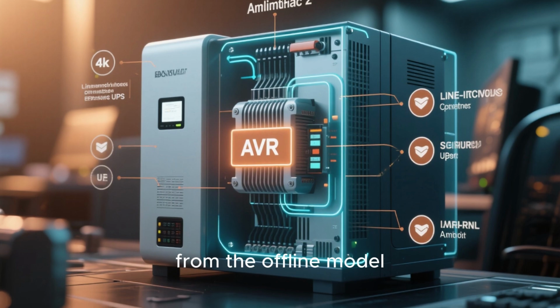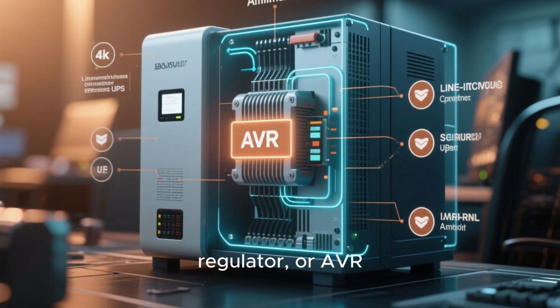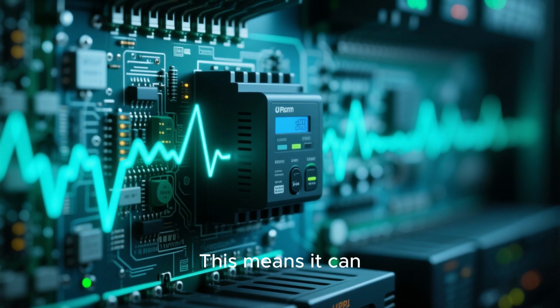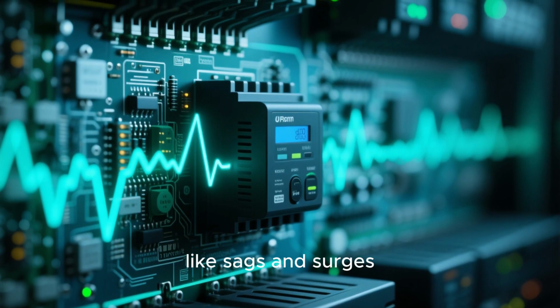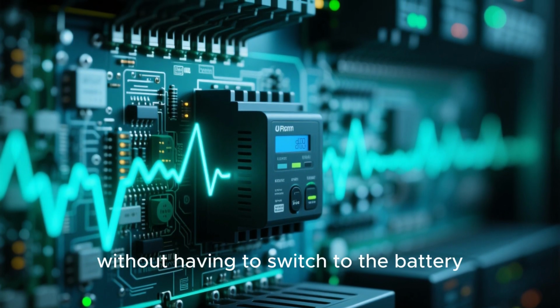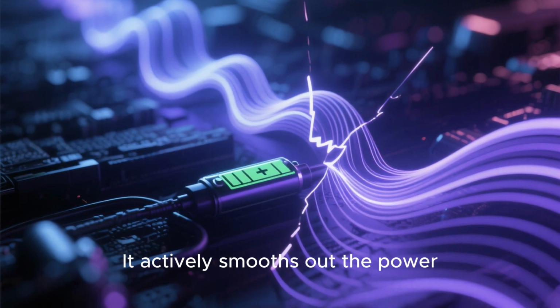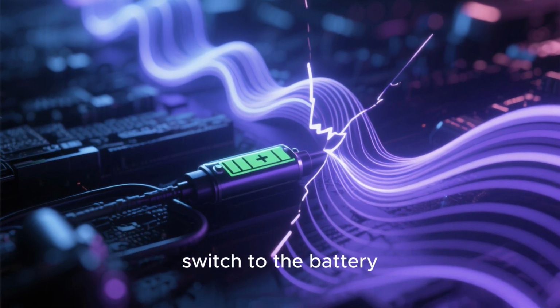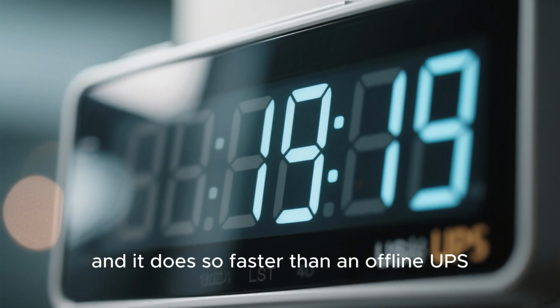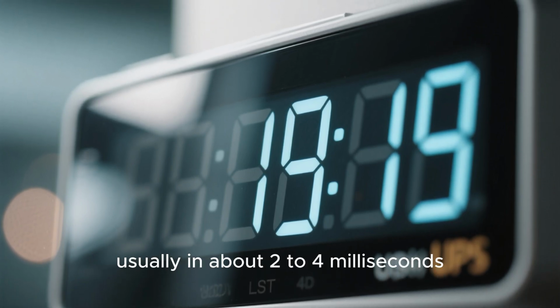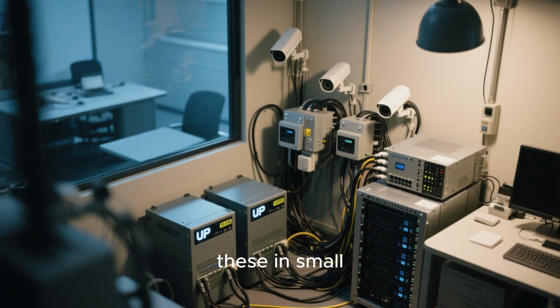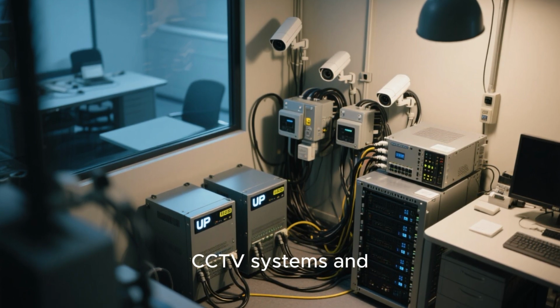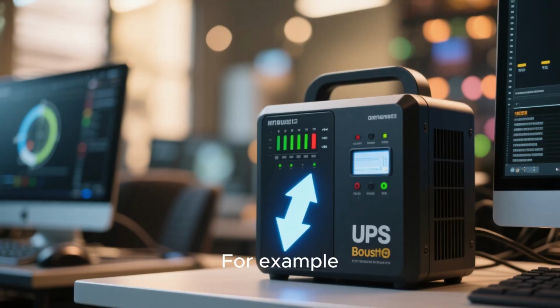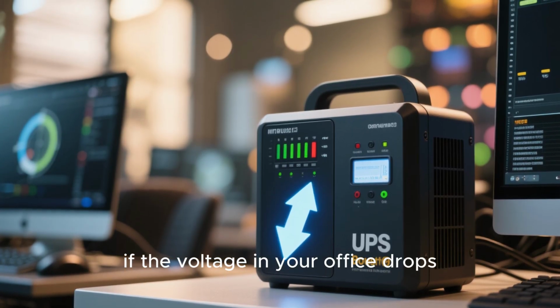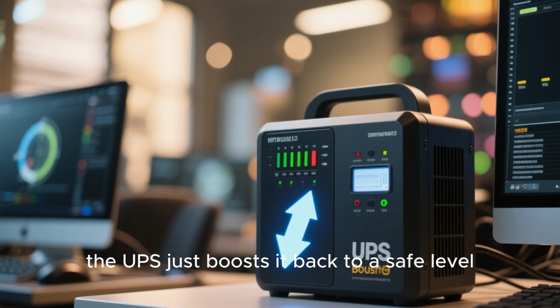Next up is the line interactive UPS. This is a step up from the offline model. It includes an automatic voltage regulator, or AVR. This means it can correct minor voltage fluctuations, like sags and surges, without having to switch to the battery. It actively smooths out the power. Only during a complete outage does it switch to the battery, and it does so faster than an offline UPS, usually in about 2 to 4 milliseconds. You'll often find these in small offices, protecting CCTV systems and small servers. For example, if the voltage in your office drops, the UPS just boosts it back to a safe level, protecting your computers.